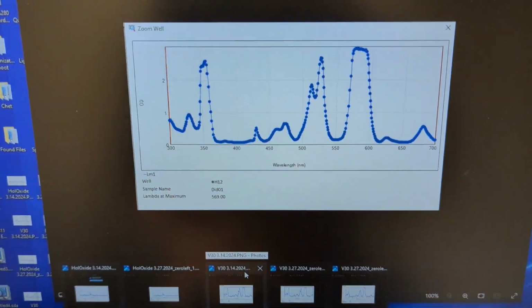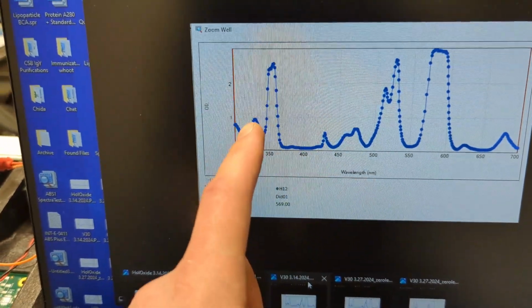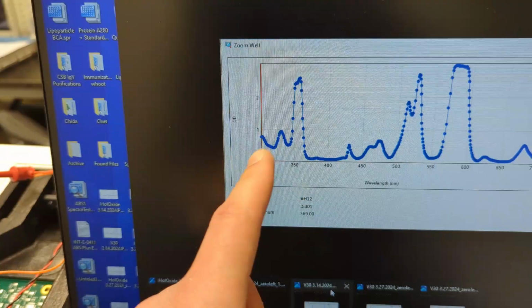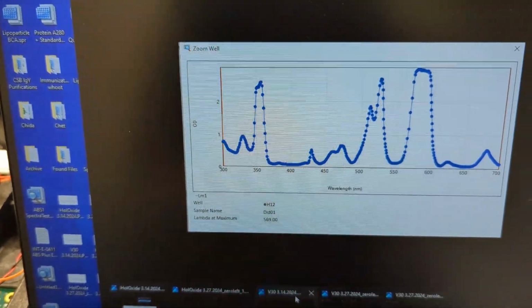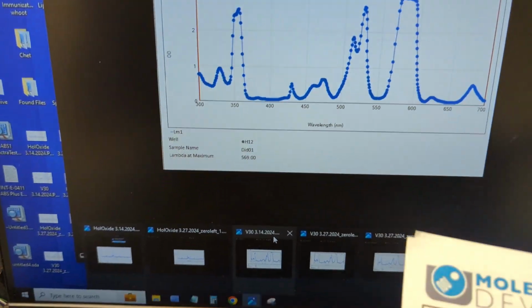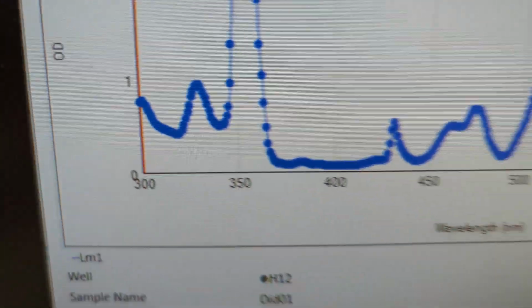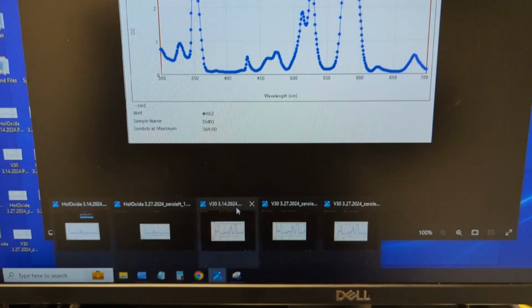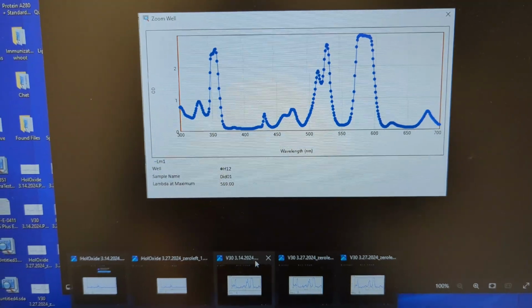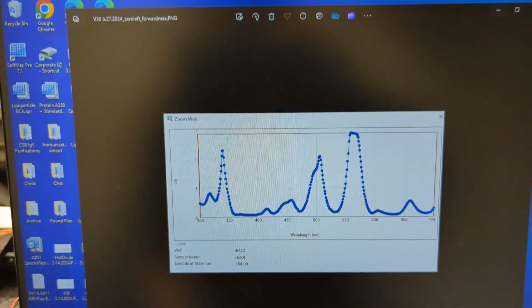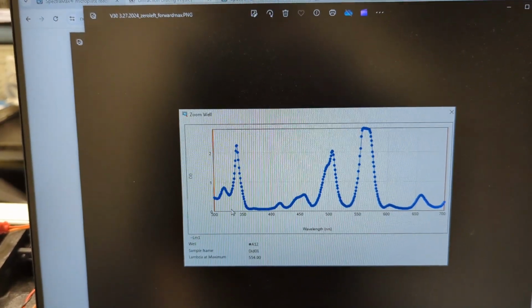All right, so this is the V30 passing. It's a little bit harder to make out this one, but peak number 1 should be roughly 330 nanometers. Peak number 2, I believe I have it, yeah, here it is. So yeah, peak number 1 is 330. That's that guy right there. Peak number 2 is roughly 431. That's this one right here. And then peak number 3 is 681.7. That's that guy right there. All right? And this is a passing run. They need to be plus or minus 3 nanometers, and that's passing.